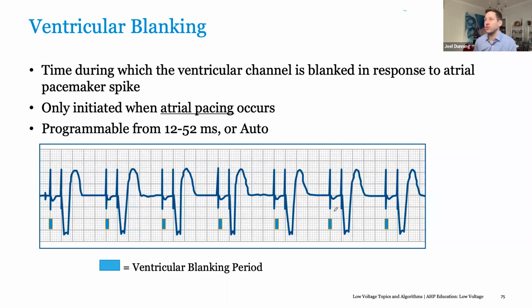That brings us to our ventricular timers. So just like we had blanking in the atrium, we also have blanking in the ventricle as well. This is to avoid any kind of oversensing of the atrial pace, especially on the ventricular channel. It could be very detrimental to basically sense that atrial spike. What you could see occurring is the device could see the atrial spike, interpret that as a ventricular event, withhold the ventricular pace, and you could just have atrial pacing all day long with no accompanying ventricular pacing. So as a result, we tell the device just to cover its eyes for a period of time after we pace to avoid any kind of inappropriate inhibition of the device.